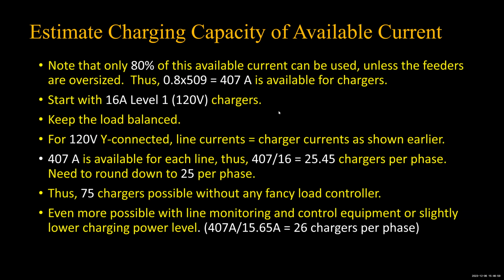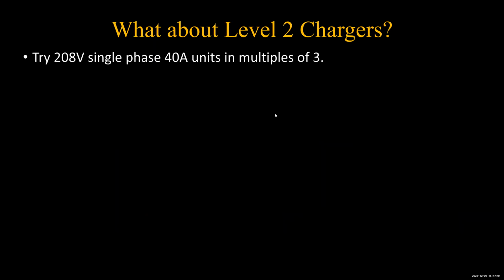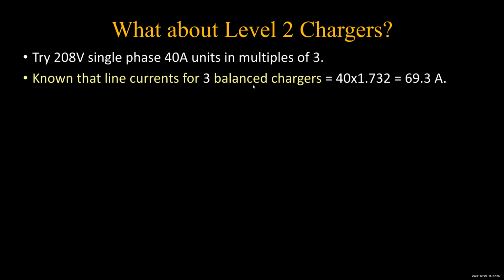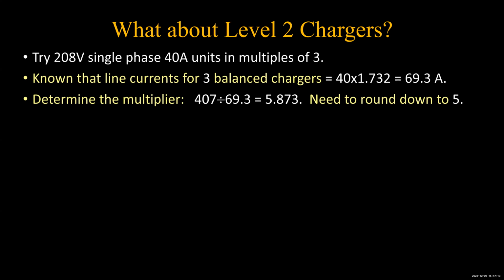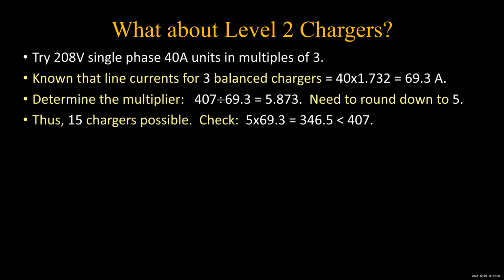We can do the 16 amp level 1, but let's move on and see what we can do with level 2s. And if we do a 40 amp unit, multiples of 3 like we just did, we know we got 69.3 for 3 of them. We know if we have 407 amps available and we use 3 of them at 69.3, that's a factor of 5.873. So we should be able to do at least 5 rounds of 3. And so that would be 15 chargers, 5 on each phase for that 407. And we can do that experiment.